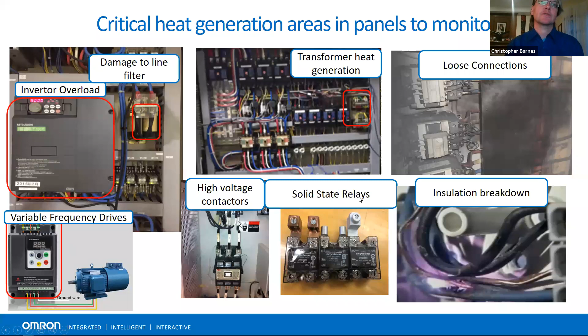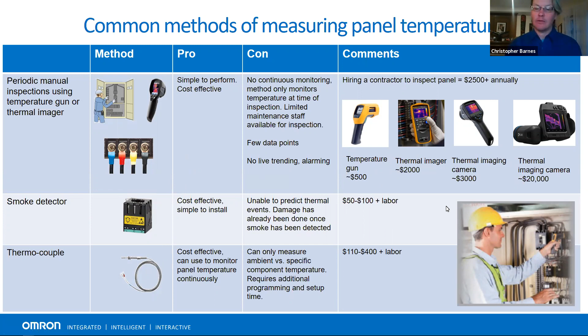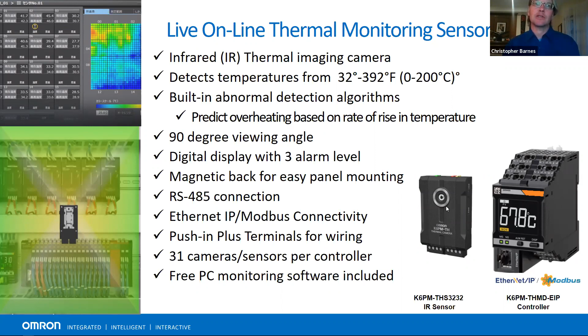So there are different ways of measuring temperatures in an electrical panel, whether with a handheld device. Most of these you're just checking as a spot check once in a while, and if you're not careful you may miss it, you could have a short 5 minutes after you've been in there. So really the better way is to have continuous data, which lines up with what we were talking about before, so you can trend it and spot issues earlier. And if you have an unpredicted failure, you can go look at the data trends and see if you should have been able to catch it.